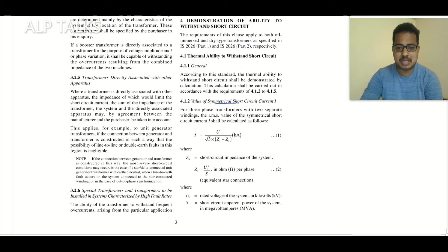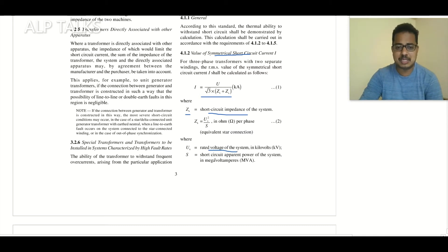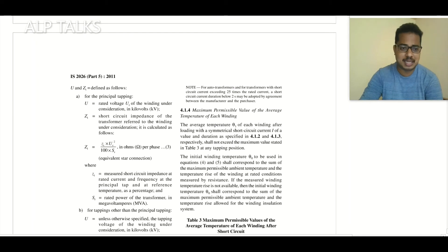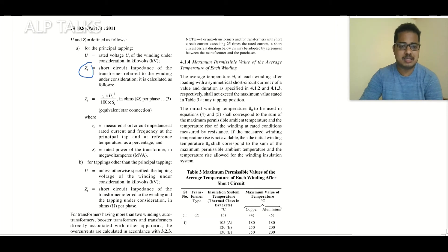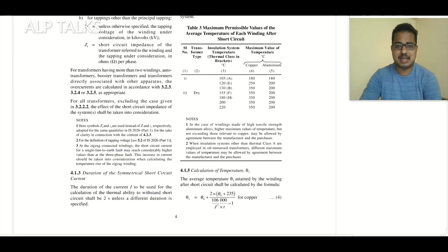For calculating symmetrical short circuit current, you can use the formula: U divided by (√3 × (Zt + Zs)), where Zs is the short circuit impedance of the system where the transformer is to be installed. Us is the rated voltage of the system, and Zs is calculated from the short circuit apparent power S. Zt is the transformer impedance converted to the base value in star equivalent.